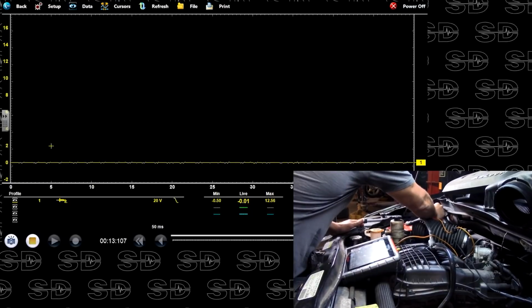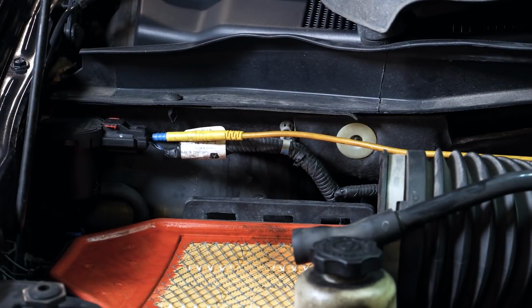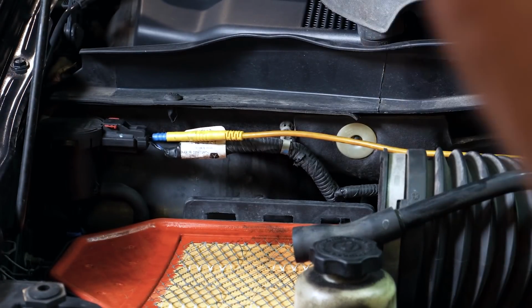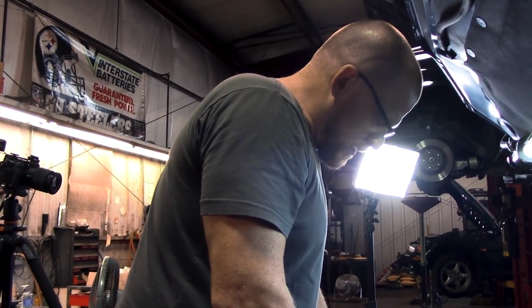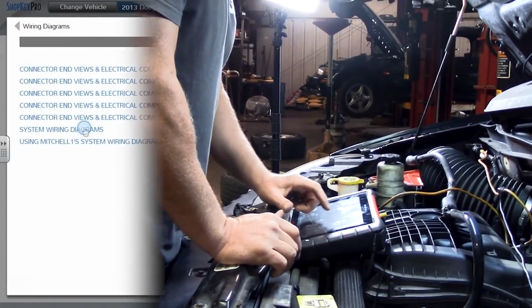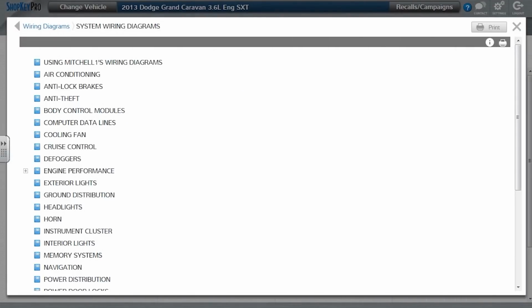Back over to my purge. Nothing on that wire, nothing on that wire. Unless that's a power side switch purge valve, I need to check a diagram. That'd be helpful to know. Let me look at a wiring diagram real quick to see how this purge valve is controlled.